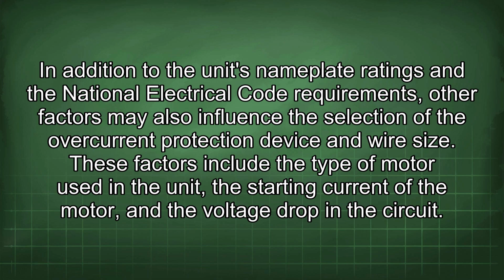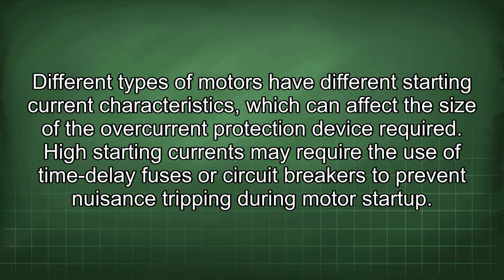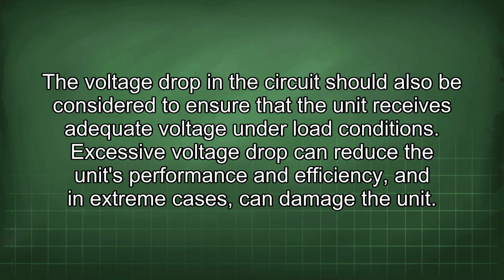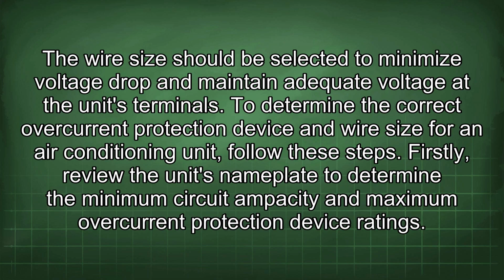These factors include the type of motor used in the unit, the starting current of the motor, and the voltage drop in the circuit. Different types of motors have different starting current characteristics, which could affect the size of the overcurrent protection device required. High starting currents may require the use of time delay fuses or circuit breakers to prevent nuisance tripping during motor startup. The voltage drop in the circuit should also be considered to ensure that the unit receives adequate voltage under load conditions. Excessive voltage drop can reduce the unit's performance and efficiency, and in extreme cases, can damage the unit. The wire size should be selected to minimize voltage drop and maintain adequate voltage at the unit's terminals.